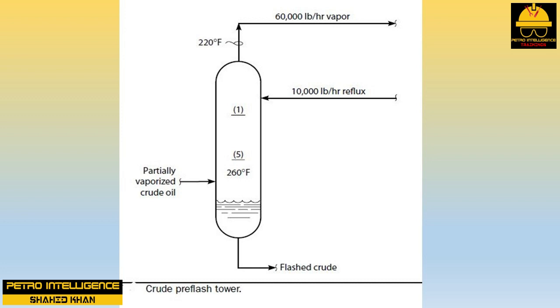But what happened to the sensible heat content — the heat represented by the temperature of the vapors leaving the tower? As the vapor is cooler, the sensible heat content decreased. Where did this heat go? A small part was picked up by the extra liquid draining from the top tray (the extra reflux), but the liquid flow is too small to carry away much heat. The main reason the vapors leaving the top tray are cooler is vaporization — the sensible heat content of the flowing vapors is converted to latent heat of vaporization.